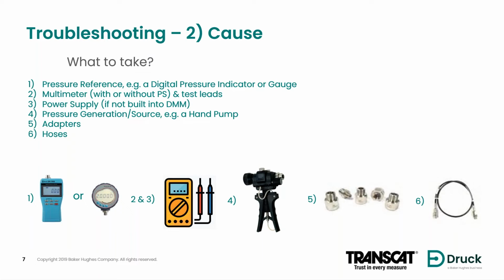We'll need a multimeter, preferably one with a built-in power supply, so that we could energize the circuit and/or the unit that we're testing. Obviously, some test leads. If we have a multimeter that doesn't have a power supply, we'll need to bring one of those. We'll have to have some way of generating pressure, most commonly a hand pump, although there are other options. And then we'll need some adapters, some way to connect our equipment, our pressure references, our multimeter, our pump to the device, and possibly hoses as well if it's a device that's in an installation that we can't remove or directly connect to.